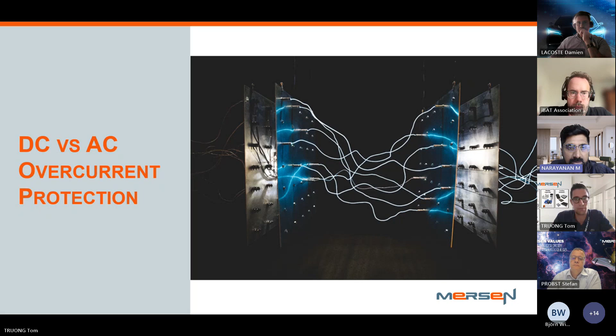In the coming slides we'll talk more about DC fuses. When it comes to DC protection specifically, there's a specific challenge about the absence of a natural zero, which makes it much more difficult for a fuse to mitigate the fault and quench the arc. So when we compare an AC wave, shown on the left, to the right-hand side you have the DC fault current.